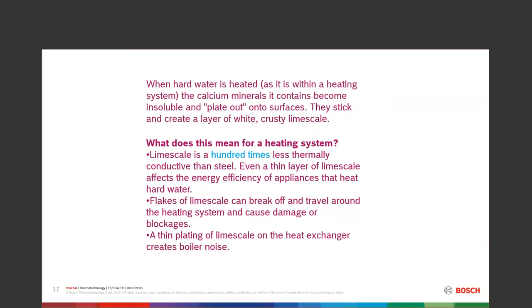If we've got a half inch of limescale in there, our passages won't be able to move water — and a half inch represents about a 70% drop in efficiency. Think about that: using a thousand gallons of fuel, 700 gallons goes to waste. That's big. Part of the importance of taking care of all this at once is that it's not hard to do.